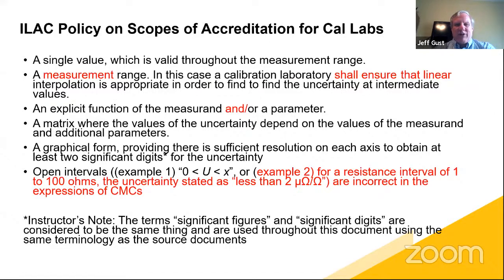In this case, the calibration laboratory shall ensure that linear interpolation is appropriate in order to find the uncertainty at intermediate values. So you might put in a slope-intercept type of equation to say, well, from 0 to 1,000 volts, I'm 20 parts in 10 to the 6 plus 5 microvolts. And you could figure out what your uncertainty would be at 1 volt, 10 volts, 50 volts, 100 volts, whatever point, using that function. And it was agreed that a linear interpolation, not trying to get to higher order polynomials within a range, was really an appropriate thing to do.